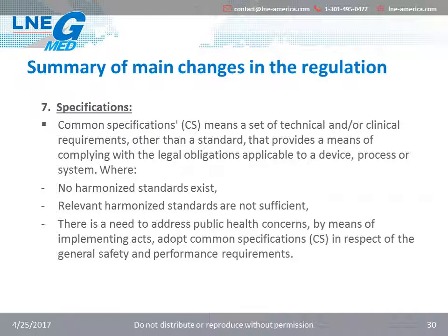To continue with the main changes in the regulation, we will talk about change number 7, specifications. Common specifications, referred to as CS, means a set of technical and/or clinical requirements, other than a standard, that provides a means of complying with the legal obligations applicable to a device, process, or system. Where no harmonized standards exist, or relevant harmonized standards are not sufficient, and if there is a need to address public health concerns by means of implementing acts, adopt common specifications in respect of the general safety and performance requirements.